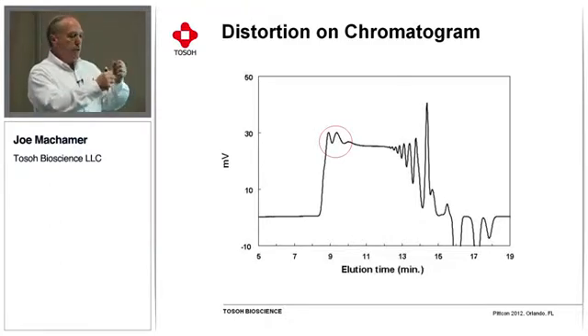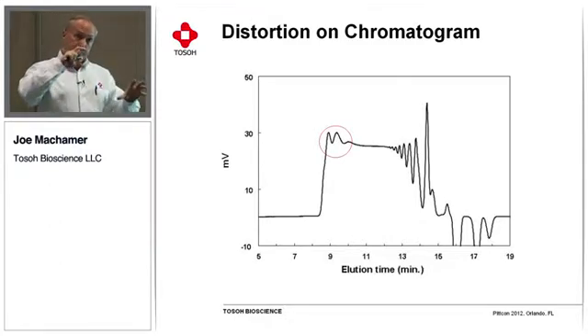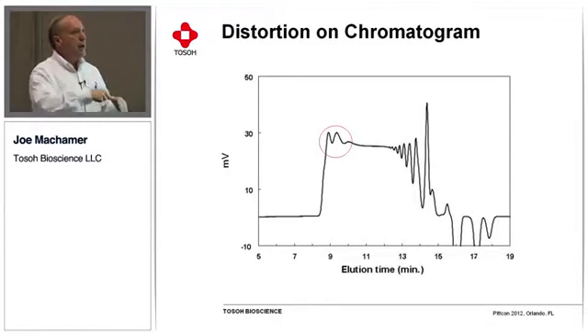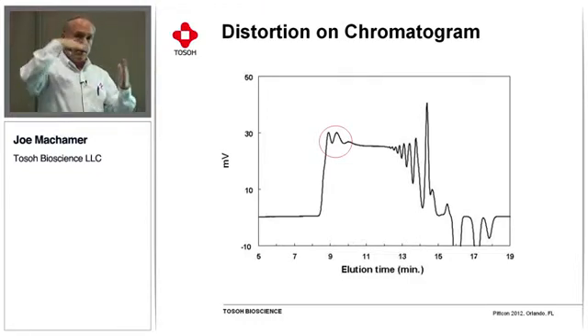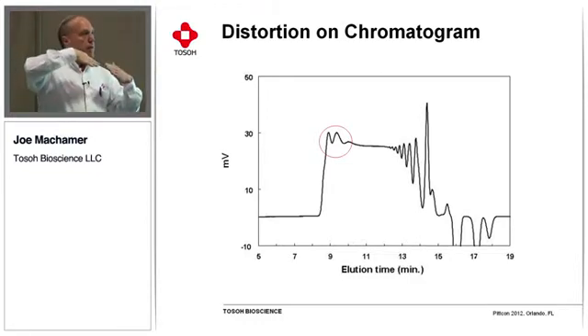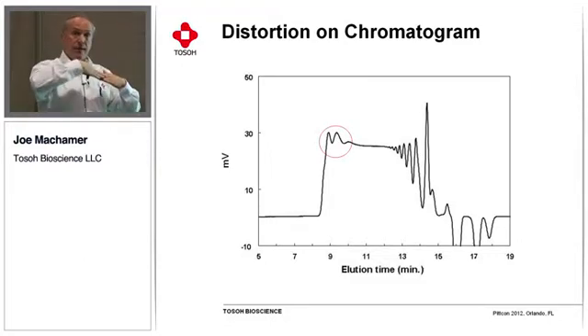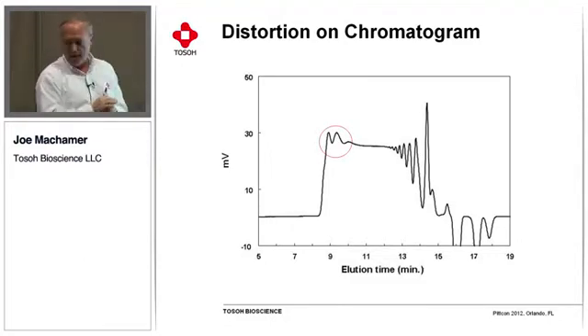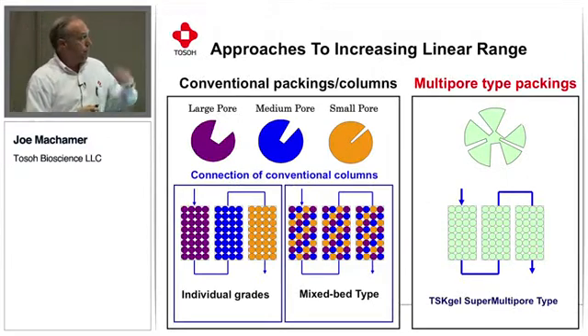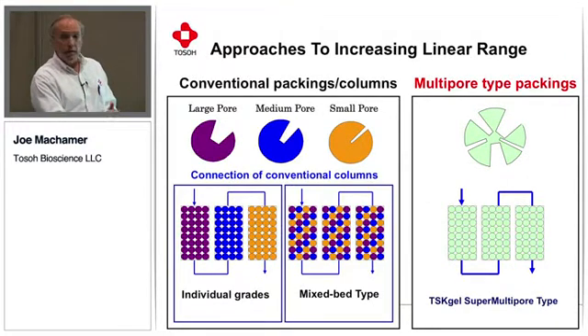If the individual columns that you're attaching to each other, or the beads that you're mixing together into a mixed bed column, aren't on the same slope in terms of their linear calibration ranges, you can end up getting artifacts in the chromatography that will look like peaks, but really are just the fact that these linear ranges are not overlaying smoothly enough to give you decent data. So because of that problem, Tosoh developed a multi-pore type of packing.